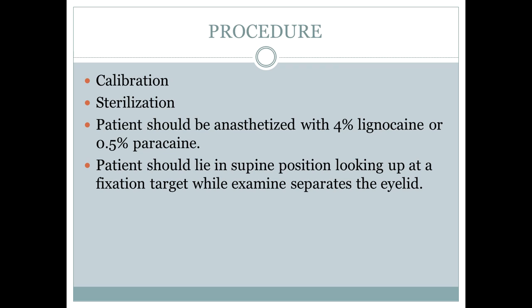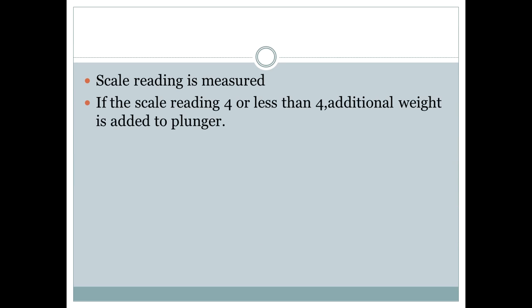Then you have to separate the patient's eyelid and place the footplate over the cornea. Measure the scale reading. If the scale reading shows 4 or less than 4, then you have to add the additional weights of 7.5 gram or 10 gram to the plunger and repeat the whole procedure again.